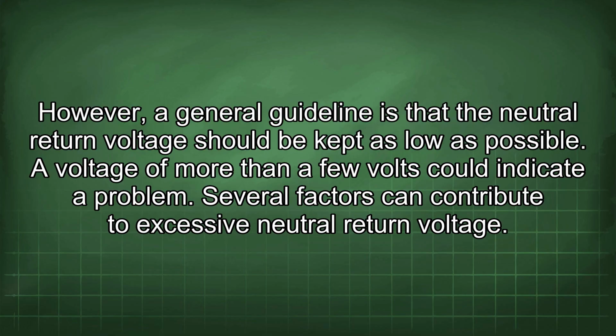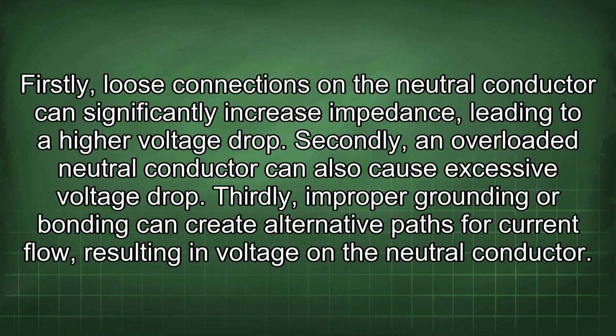Several factors can contribute to excessive neutral return voltage. Firstly, loose connections in the neutral conductor can significantly increase impedance, leading to a higher voltage drop. Secondly, an overloaded neutral conductor can also cause excessive voltage drop. Thirdly, improper grounding or bonding can create alternative paths for current flow, resulting in voltage on the neutral conductor.